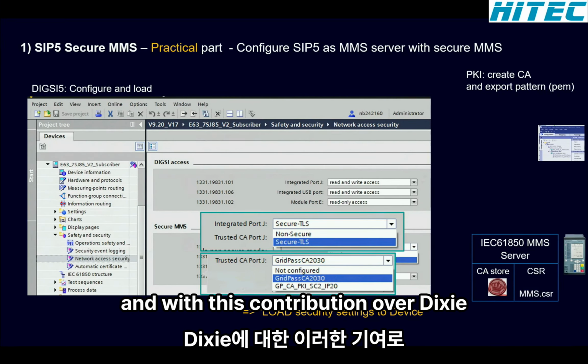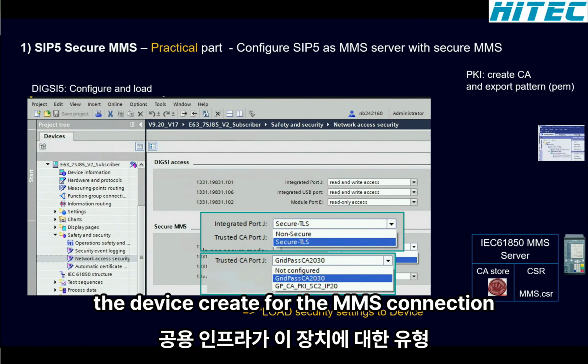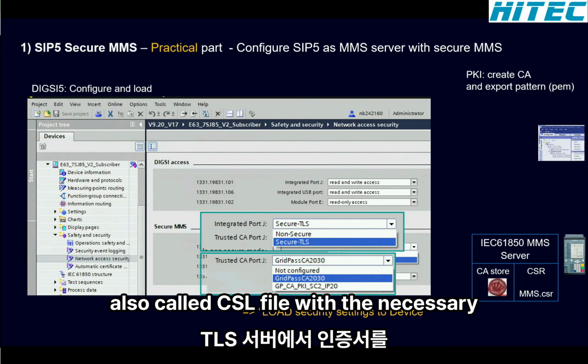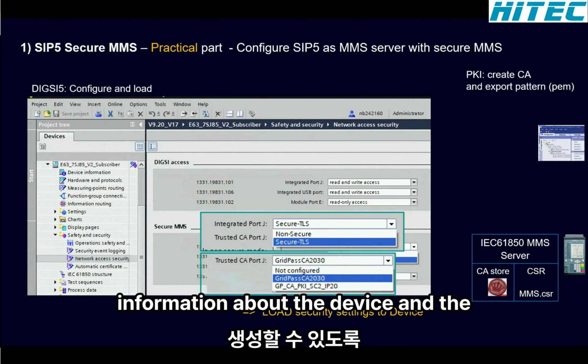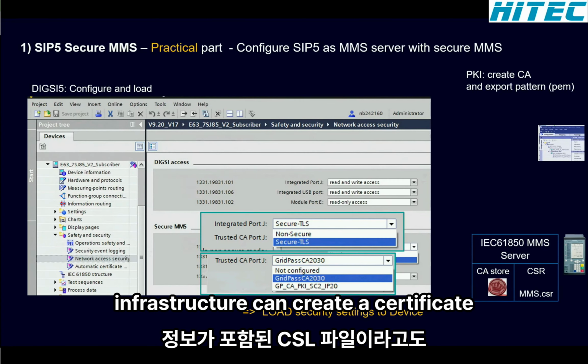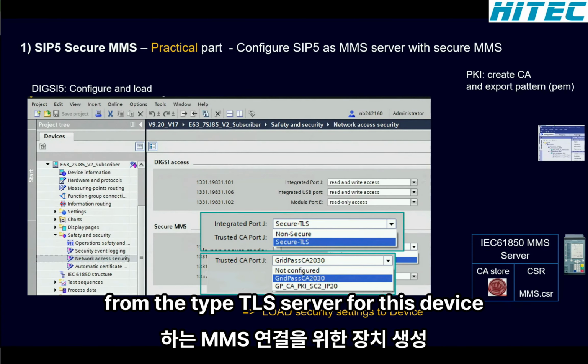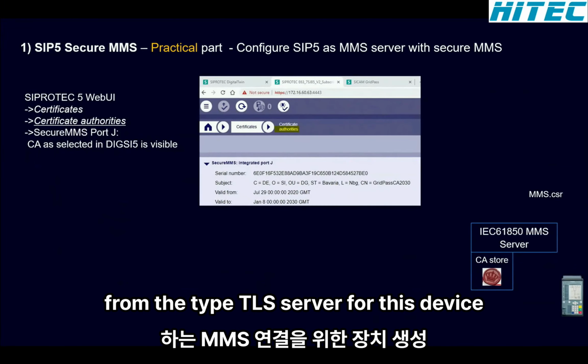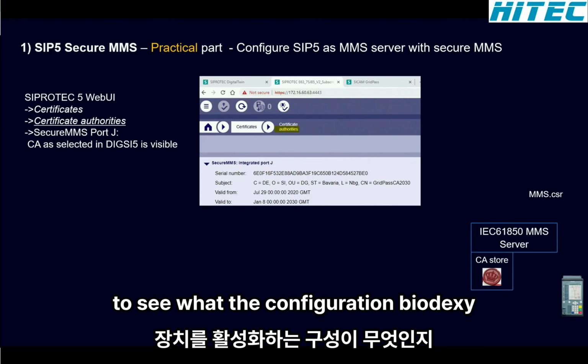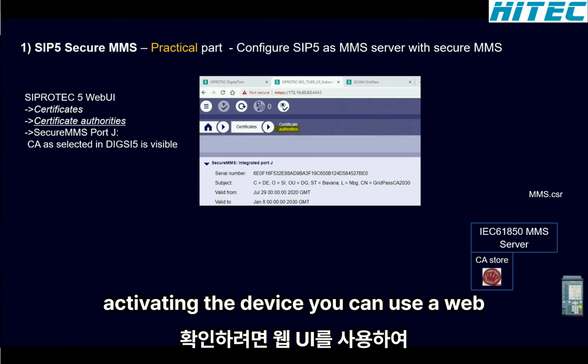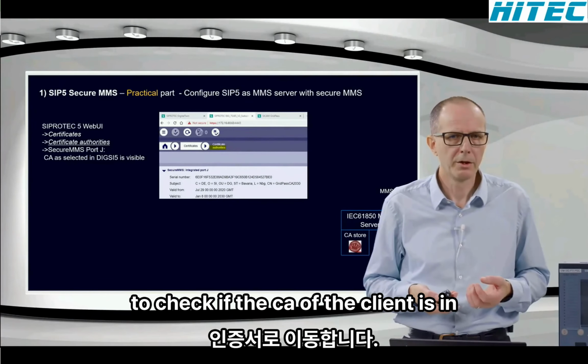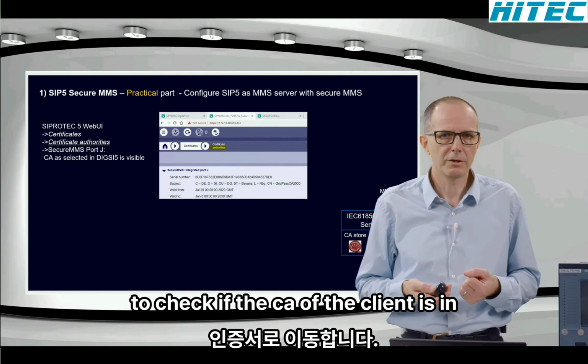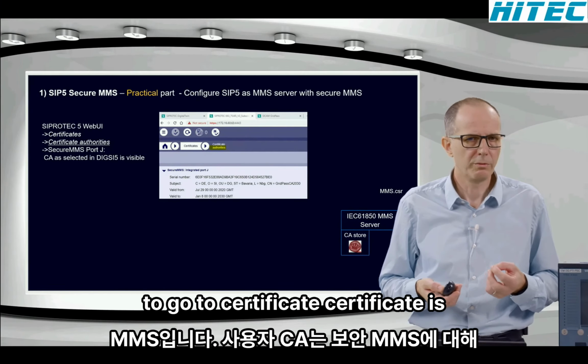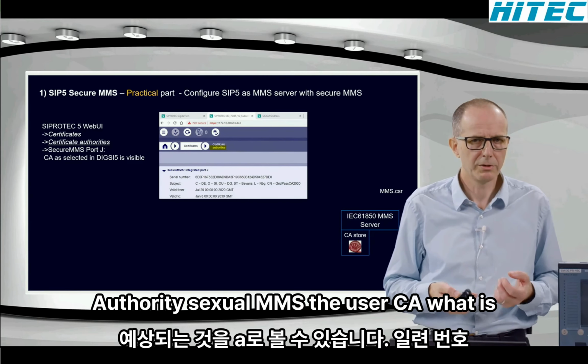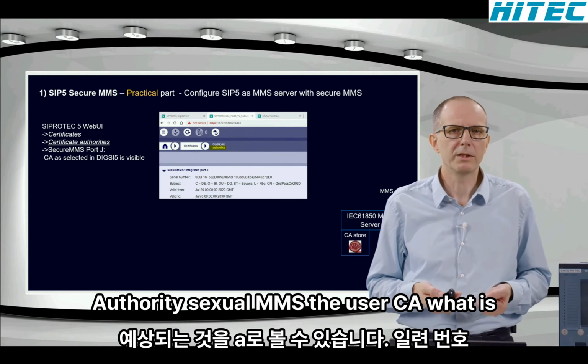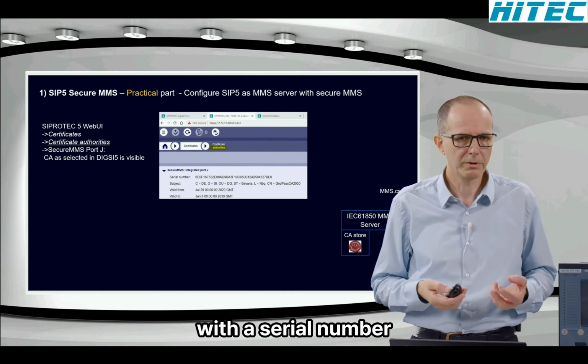With this configuration over DIGSI5, the device creates for the MMS connection a so-called CSR file, with the necessary information about the device and the protocol, so that the public key infrastructure can create a certificate of the type TLS server for this device. To see what the configuration via DIGSI5 activated in the device, you can use the web UI to check if the CA of the client is in the repository. Go to Certificate, Certificate Authority, Secure MMS; the user CA that is expected for the secure MMS is visible with a serial number.